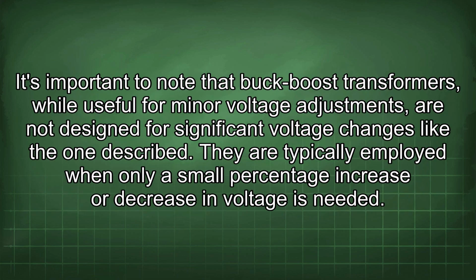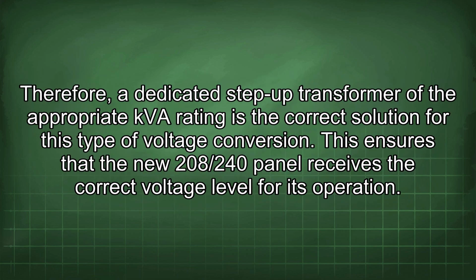It's important to note that buck-boost transformers, while useful for minor voltage adjustments, are not designed for significant voltage changes like the one described. They are typically employed when only a small percentage increase or decrease in voltage is needed. Therefore, a dedicated step-up transformer of the appropriate kVA rating is the correct solution for this type of voltage conversion. This ensures that the new 208/240 panel receives the correct voltage level for its operation.